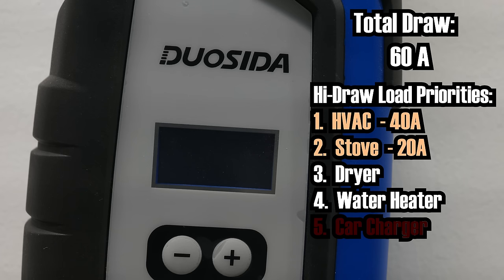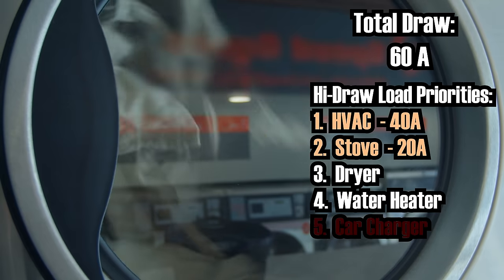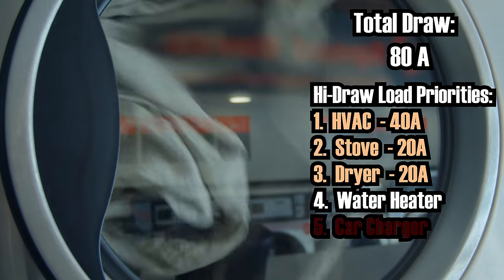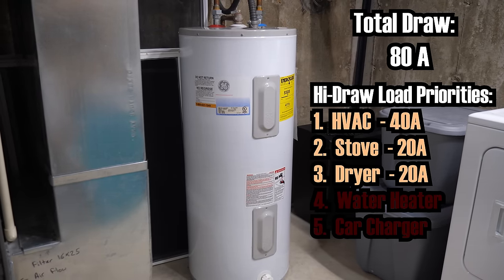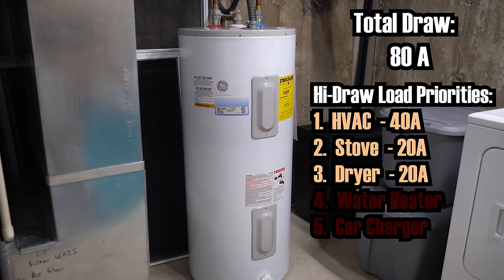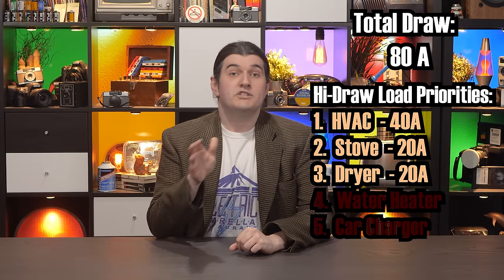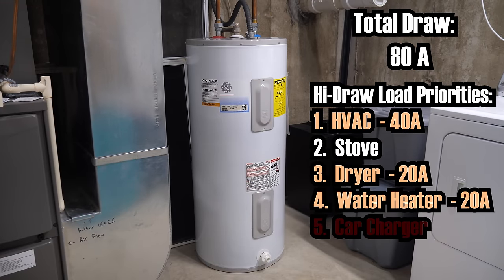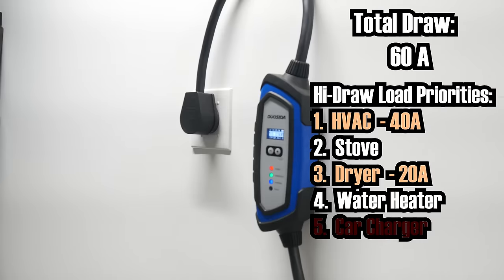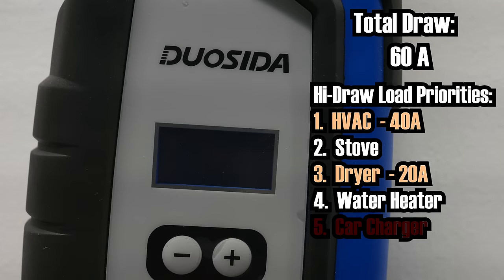You probably weren't even charging the car anyway, but we don't want a surprise 30 amps showing up right now. So now, let's say someone else in your home decides to start laundry while you're cooking. Adding the dryer to the mix while cooking a meal with the heat running pushes you up to 80 amps. And at this point, your panel takes further action, temporarily disabling the water heater — which, by the way, is a perfect load to kill, as even if it stays off for several hours, the water in the tank will stay piping hot and you can still use it as you please. It's literally a battery, just a hot and wet one. Once you're done cooking, the panel recognizes the load from the stove has dropped off, so it re-enables the water heater, recharging that wet-hot battery if needed. The car charger remains locked out though, as the higher priority dryer is still in use and the heat is still running. Once the laundry's done, your car is free to charge again.